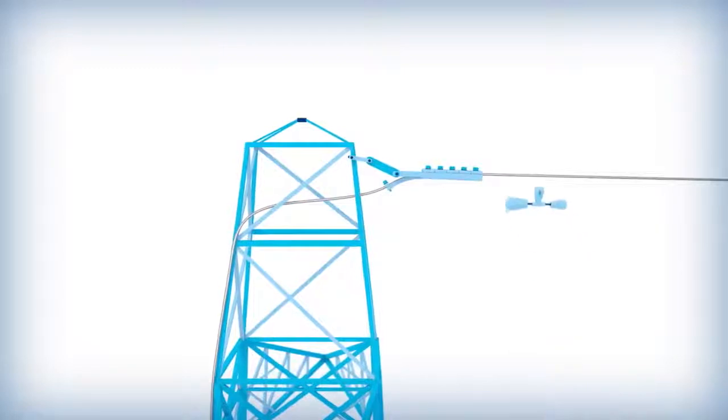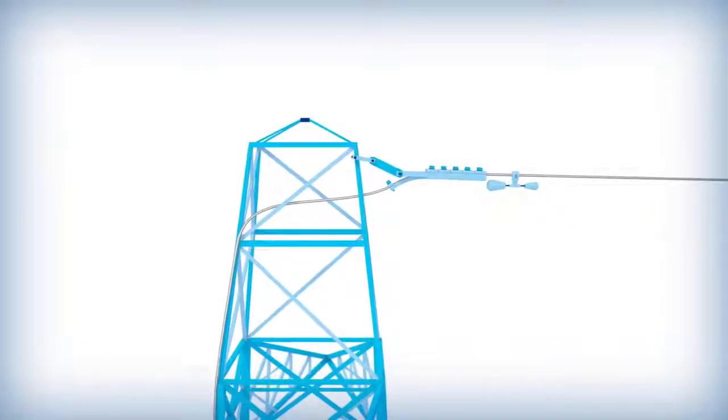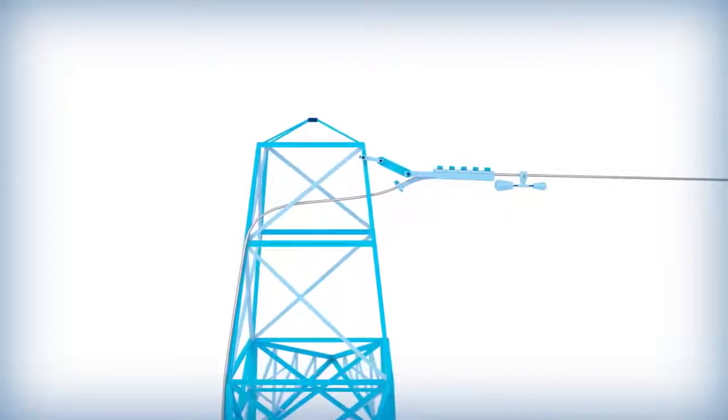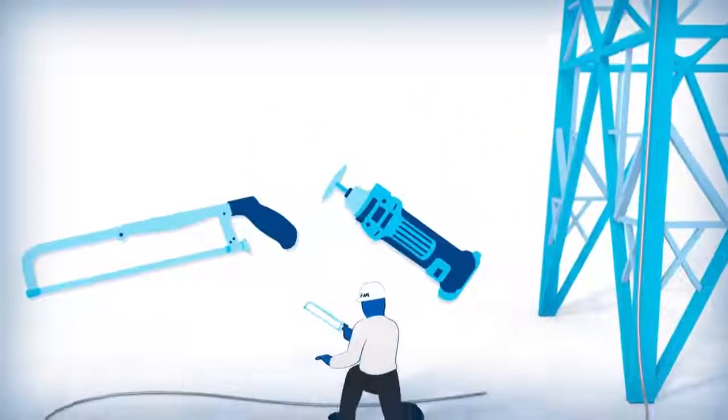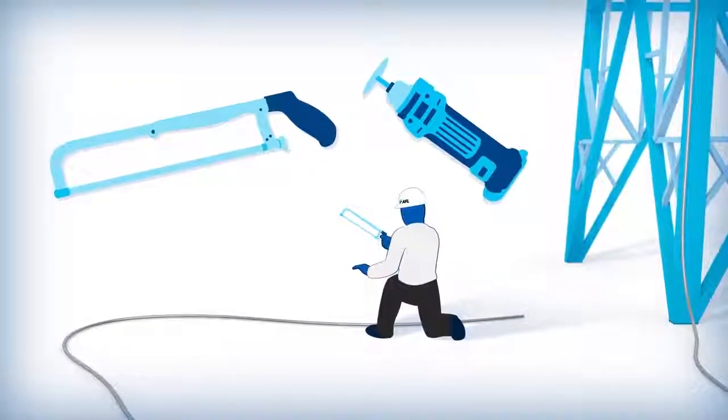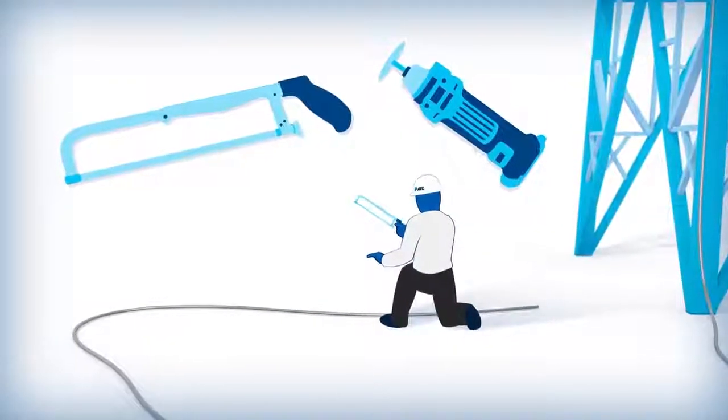If vibration dampers are required, they should be placed on the OPGW immediately after clipping in. When cutting the OPGW, a hacksaw-type cutter or rotary saw should be used to avoid crimping the cable and damaging the optical units.